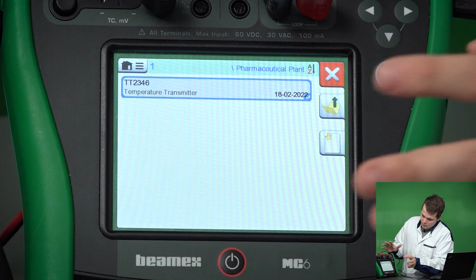And we're out in the field. We can click on Document and Calibrator, and here we'll find our job. In this case, we will be calibrating a temperature transmitter, which is convenient because the MC6 can simulate the temperature for the transmitter and then also read the current that is coming out of the transmitter, which means that the MC6 can do this calibration completely automatically.